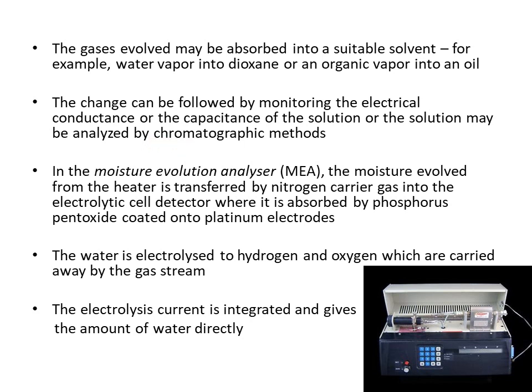Another technique is the Moisture Evolution Analyzer (MEA). The moisture evolved from the heater is transferred by a nitrogen carrier gas into an electrolytic cell detector, where it is absorbed by phosphorus pentoxide (P₂O₅), which is hygroscopic in nature. This phosphorus pentoxide is coated onto platinum electrodes. The absorbed water is then electrolyzed to hydrogen and oxygen, which are carried away by the gas stream, and the electrolysis current is measured.